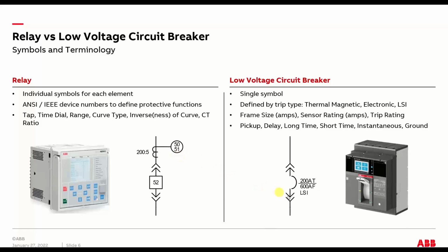The LSI would roughly equal, the LS would be the 51 device, and the I, or instantaneous, would be the 50. So 50 is instantaneous, 51 is time overcurrent. This is actually an important slide because one of the big things I'm trying to convey in this presentation is this terminology. For a protective relay, the settings are called tap, time dial, range, curve type, inverseness of a curve, CT ratio. Equivalently in the low voltage world, you'd have things called pickup, delay, long time, short time, instantaneous, ground.